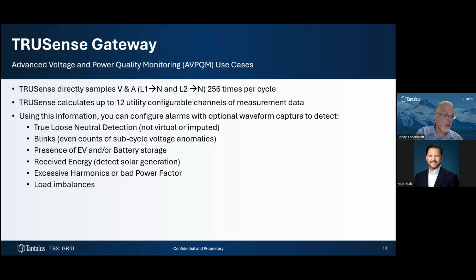We can detect the presence of EV or battery storage because we're sampling every cycle, and we know that demand for a 2-3 hour period has never dropped below a certain amperage. So we know we've got a large load that is not a dryer, not a heater, but certainly battery storage or an EV.